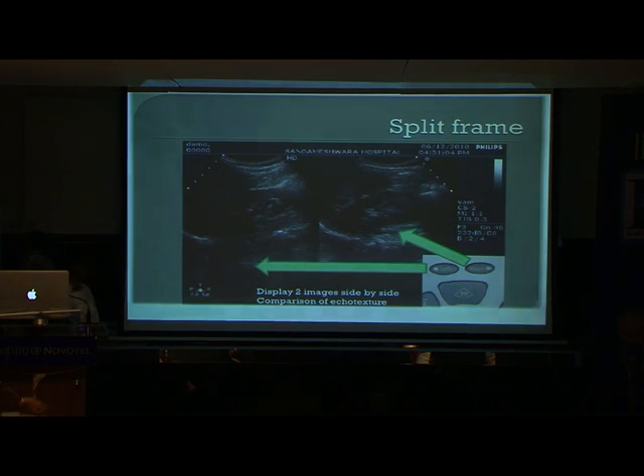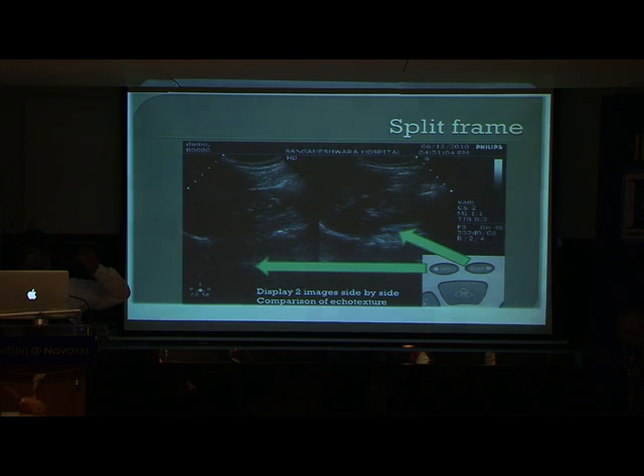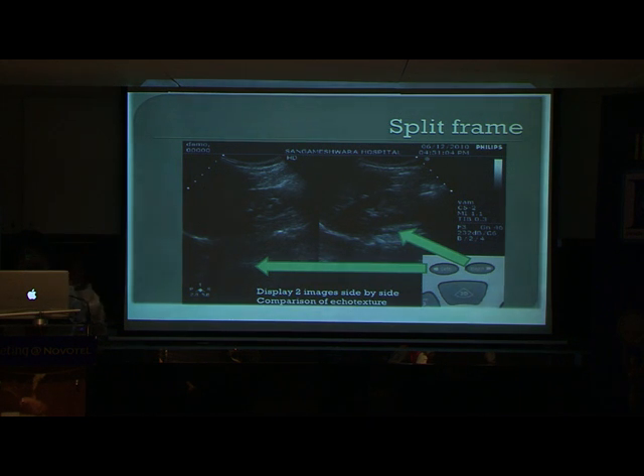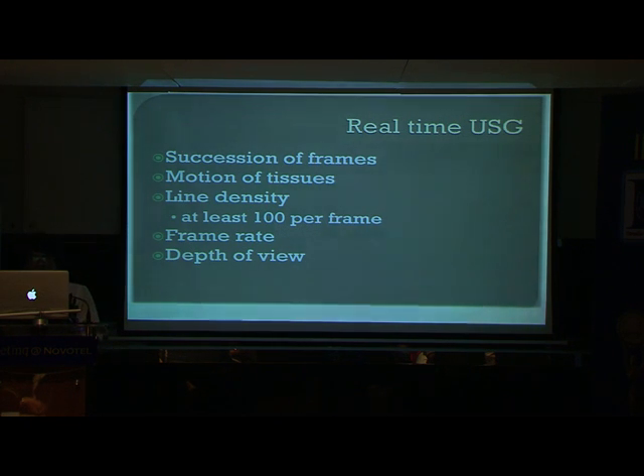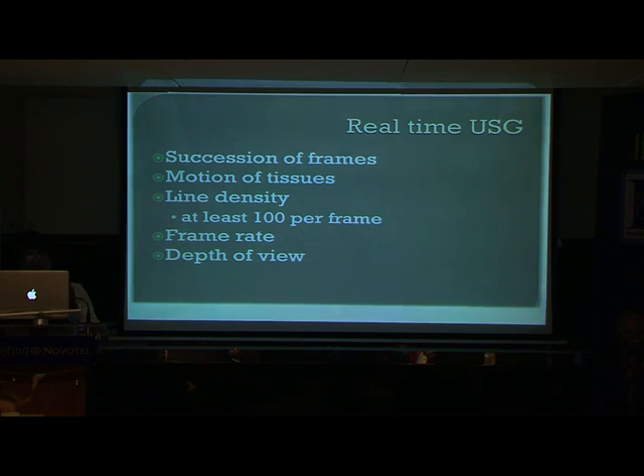Split-frame imaging: you keep the reference frame on the left-hand side and the live frame on the right-hand side. This way, you always know where you are going and where the target is for needle placement — for example during a kidney biopsy. You match the live image with the intended target on the reference frame. Real-time imaging: we see an image at 15 to 30 frames per second, giving live imaging. All these are technical parameters to learn when you buy a machine and begin practice.